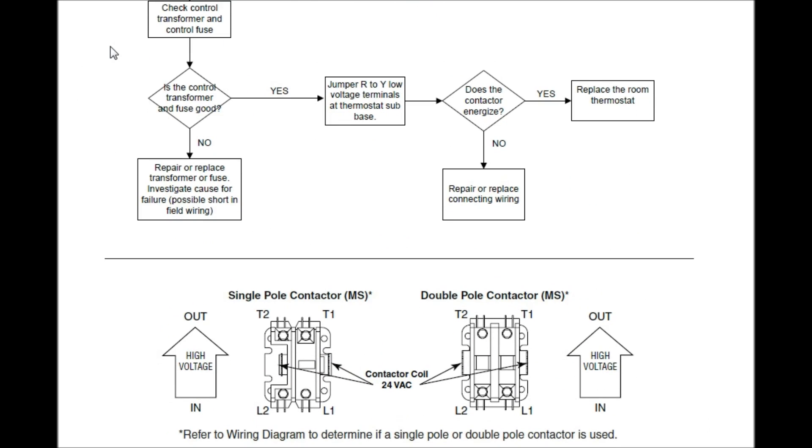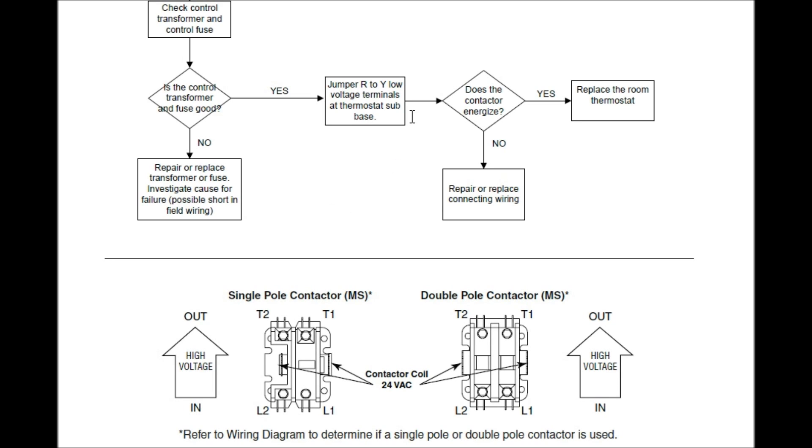Check control transformer and control fuse. Is the control transformer and fuse good? Yes. So now what it's telling us is we need to go in there to the thermostat. We need to jump around the R to Y low-voltage terminals at the thermostat subbase. Does the contactor then engage? Does it pull in? Does it energize?